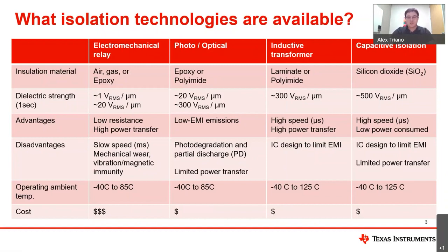Now, one of the isolation technologies we use at Texas Instruments is an inductive transformer. A laminate or polyimide material is used, which offers a high dielectric strength. High speed and high levels of power transfer can also be achieved. One trade-off is the need to design the IC to limit EMI emissions. Techniques such as Faraday shields or spread spectrum modulation are used in order to ensure EMI performance meets automotive standards. These transformers can operate at high temperatures such as 125 C and are cost effective.